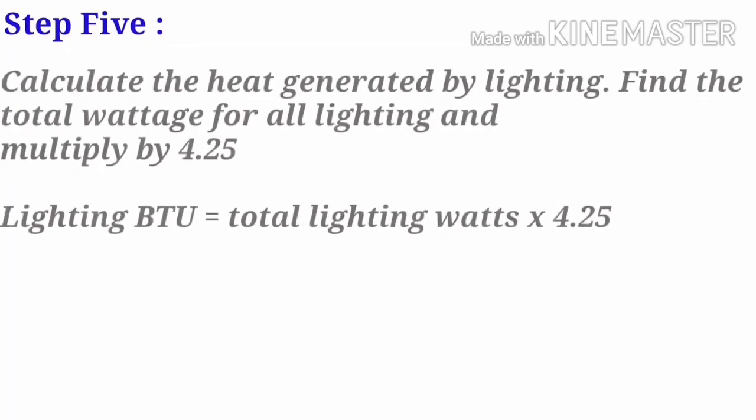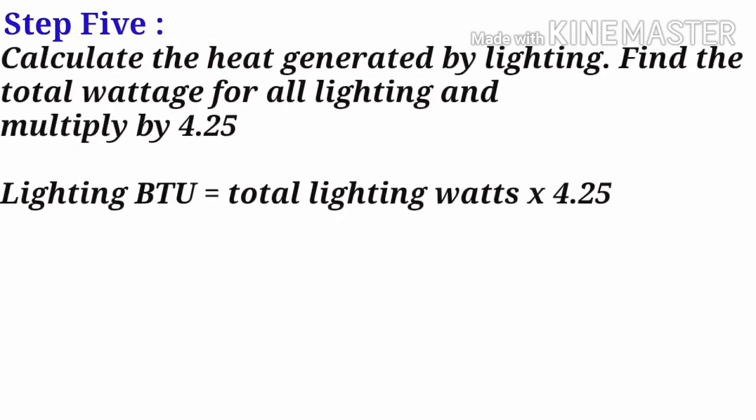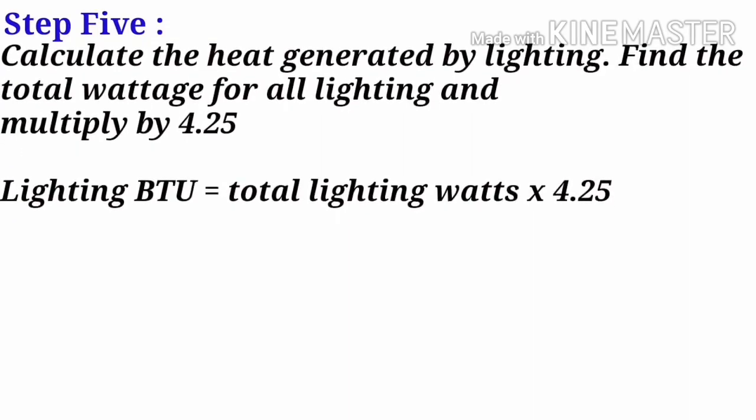Step 5: Calculate the heat generated by lighting. Find the total wattage for all lighting and multiply by 4.25. Lighting (BTU) equals total lighting watts multiplied by 4.25.